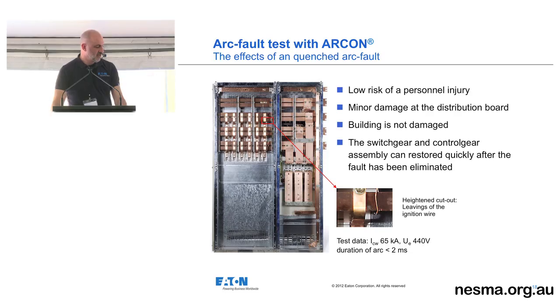Obviously we can talk about the effects of arc fault. You'll see it today. I don't know if you guys have experienced it in real life, but with the ARCON, low risk of personal injury is the major factor in all of this. Like I said before, there's minor damage to the distribution system. It can operate after you've reset the switchboard. And the switchgear and control assembly can be restored after the fault has been eliminated.